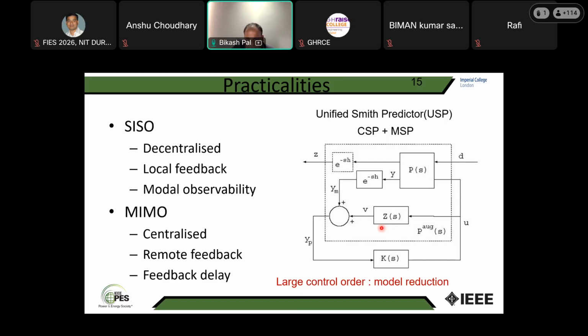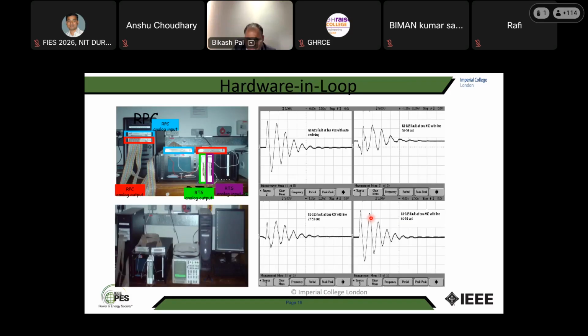But the problem with this infinity-norm-based control is that the order is very, very large: the order of the plant plus the order of the weights. If I have a large power network with, say, 100 states, I will have a 100-order controller plus the weights, so 100 to 110 order controller. That's not acceptable. So we need to go for low order, and at the same time we need to have robustness.